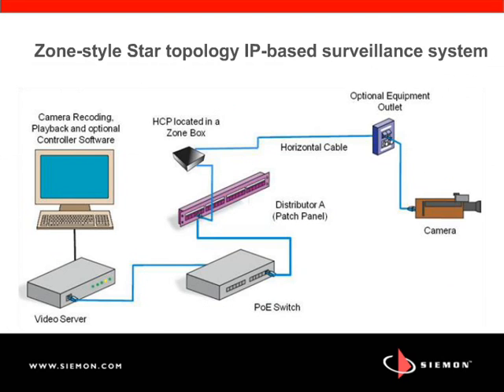Obviously, in a type of topology like this, the horizontal cable segment would be solid, and naturally, a stranded cord would be used from the optional equipment outlet to the camera. But the BAS standard does allow a provision for the optional equipment outlet to be removed from the system. And in that case, we have a direct connection from the HCP in the zone box to the camera. And I do want to emphasize that that connection should not be made with stranded cable. It should be made with solid cable.